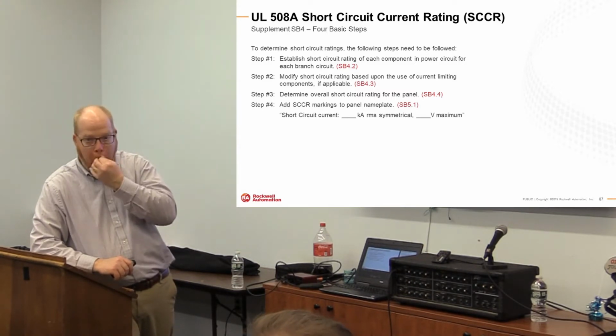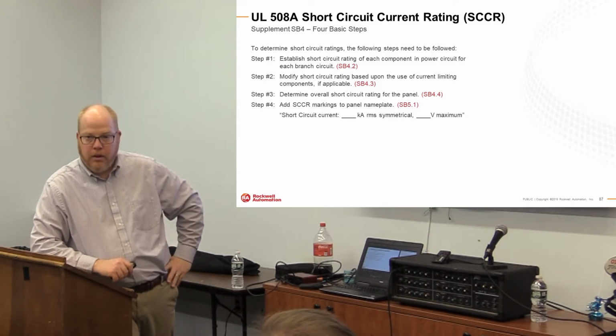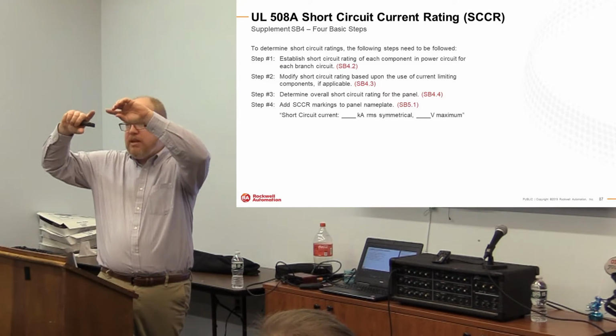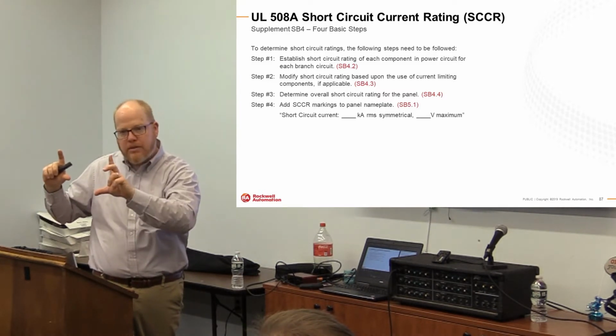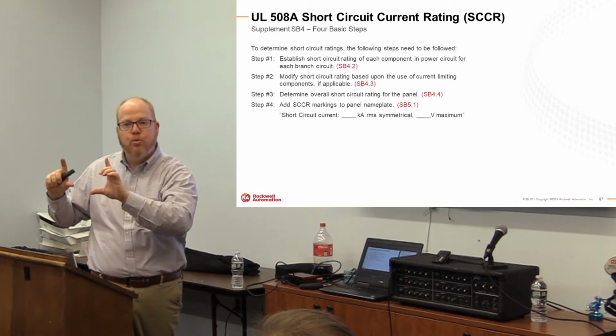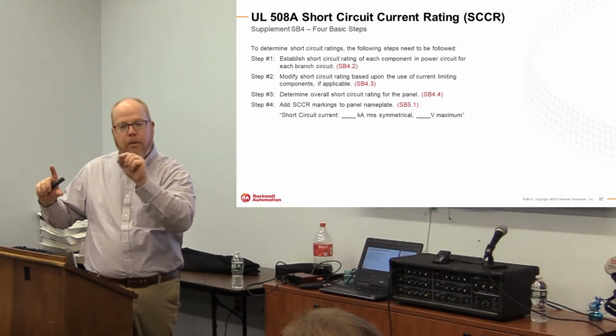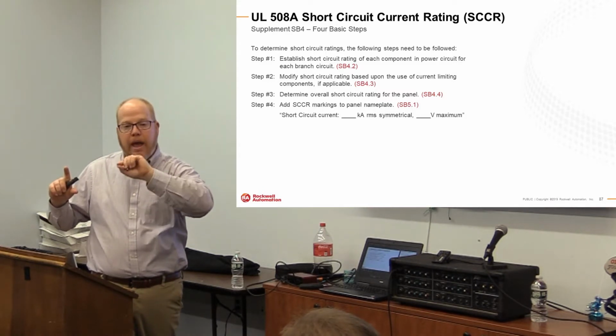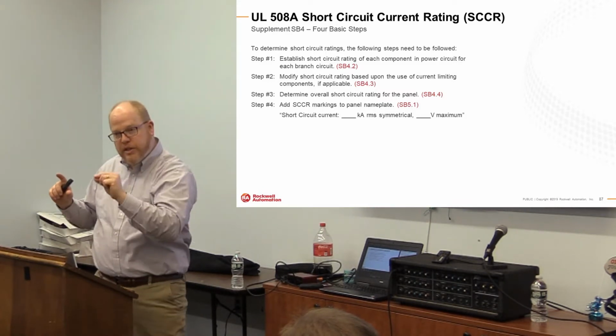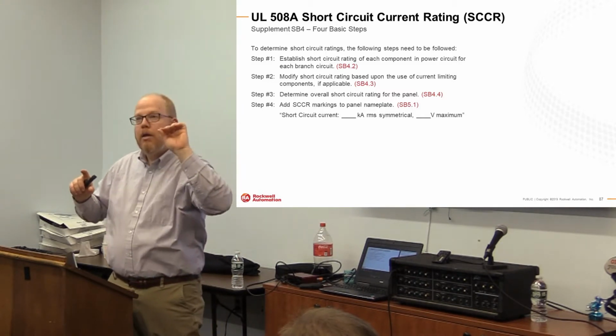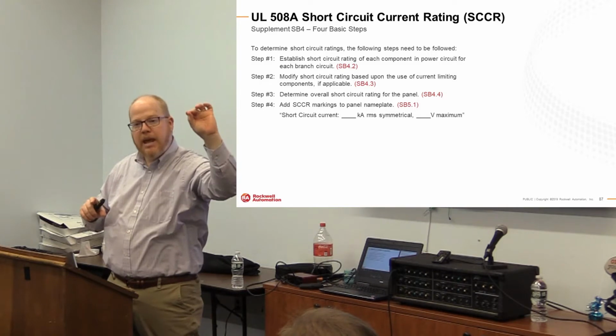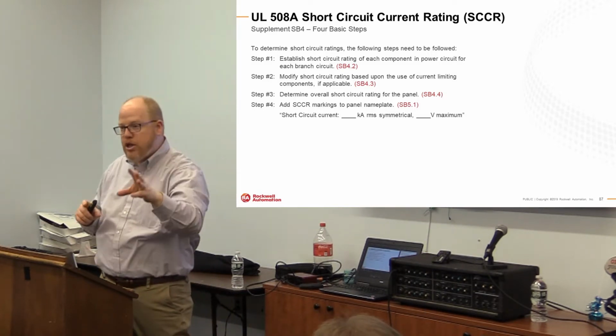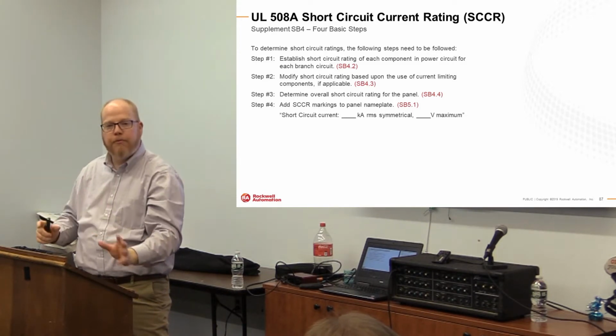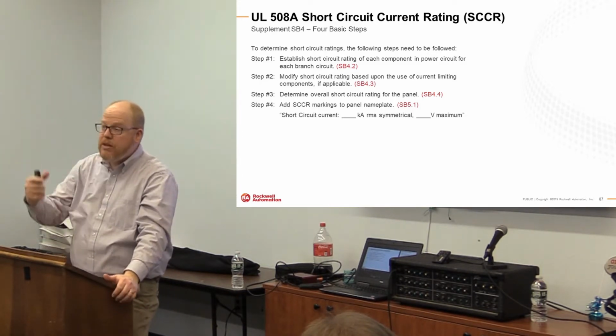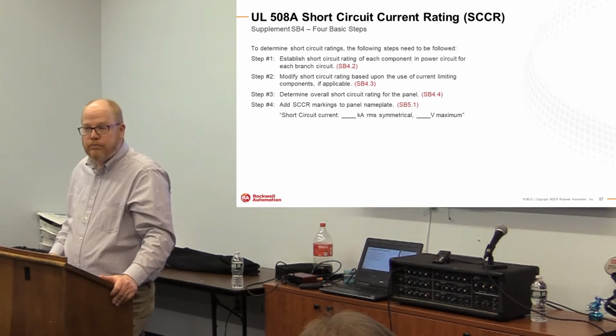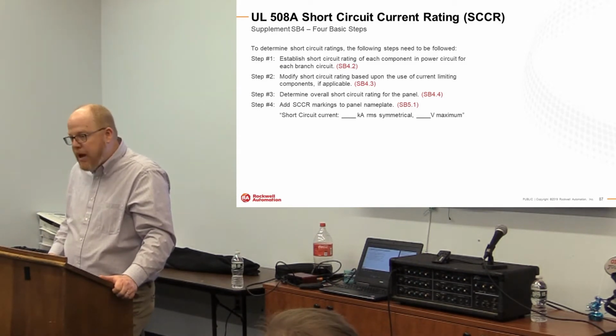of the short circuit was that they have to do it based on the installation. The only paradigm we've got is that if we're in the box, looking at only what's in the box, we can evaluate what the componentry is able to withstand from an available fault. And that's what the sticker says. Now, for the end user doing the installation, your sticker value is a piece of data they need. The available fault calculation is a piece of data they need for proper application. But your job is really only what's in the box and what available fault it can sustain without damage, based on these calculations. And we can match their feeder circuit to that rating, and then they match their feeders.